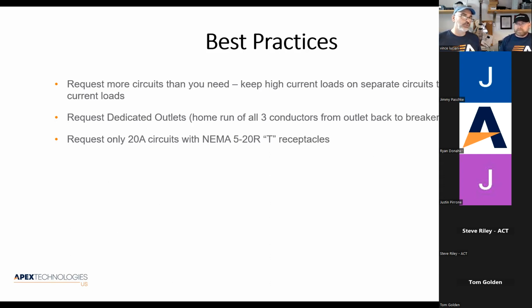Okay. When you have an isolated circuit, National Electric Code dictates that the ground wire be insulated with the green jacket, so it doesn't come in contact with the conduit. And then you got to use a special outlet. Most outlets, when you affix it to a metal junction box, it's really not a junction box, but an outlet box, right? The conduit is terminated to that, and it's got a metal nut.